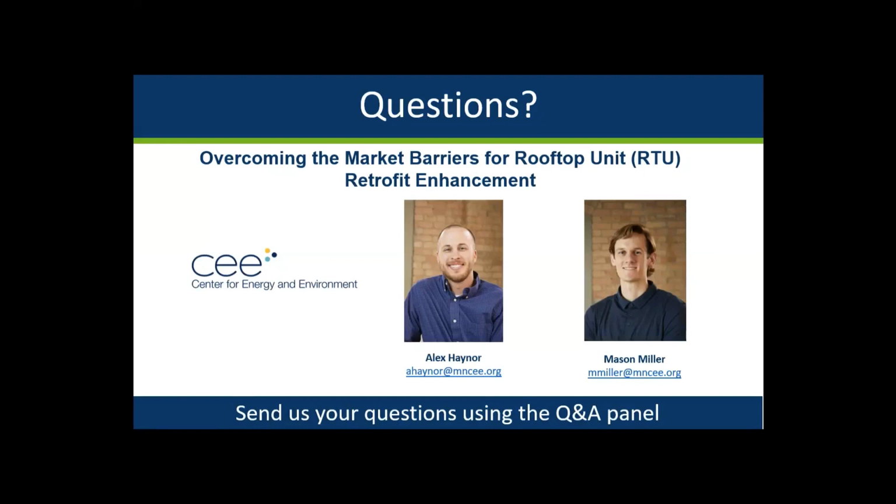So our first question today is, can you clarify what a VFD is? Sure. VFD means variable frequency drive. Really, this is a piece of equipment that is placed on an existing motor. So for the one studied in this project, that was on the supply fan, or the fan moving air throughout the system. And the goal of the VFD is really to just slow down or decrease the speed of that fan so that you don't need to provide 100% airflow during operation.